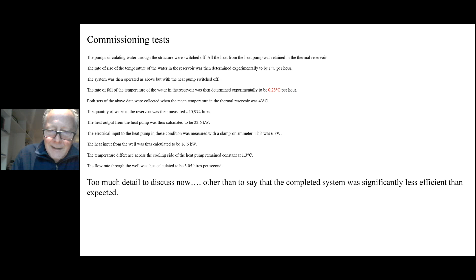And the first thing we did was we eliminated the thermal reservoir. There was a standing loss there, which is approximately equivalent to 23% of the output from the heat pump. And by doing that, we were able to eliminate delta T across the plate heat exchangers and 2 large circulating pumps. We also replaced the evaporator in the heat pump. We were concerned slightly about corrosion. There was a high, essentially sulfuric acid, content. We wanted a slightly higher flow, and we wanted to reduce the delta T.